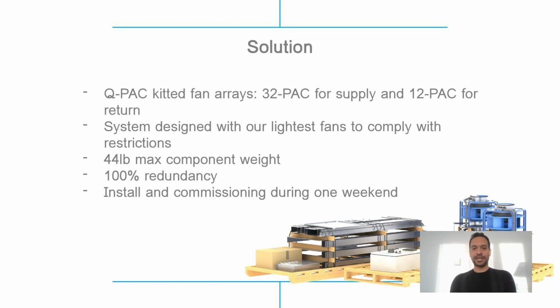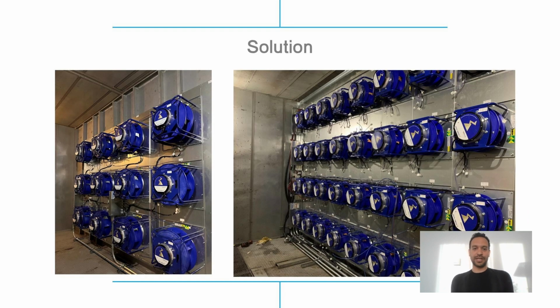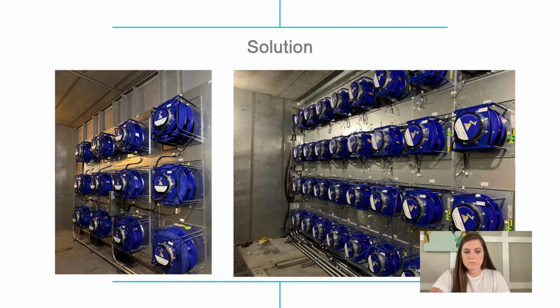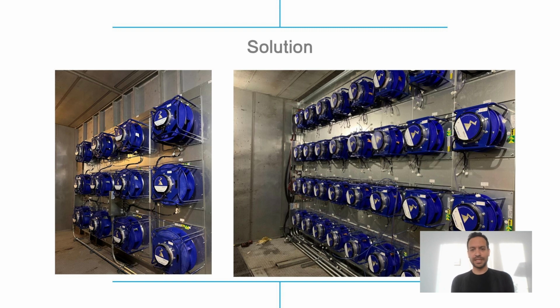And the install and commissioning happened during 1 weekend. So everything was up and running after that 1 weekend that everything was installed. A couple of pictures on the left, that is the return fan, the 12 return fans. And on the right, as you see, it's a portion of the supply fan array. You can notice the wiring isn't done, so it's mid install. So the fans are on the wall, and they're just going to do the wiring between the fans and the quick connect boxes that are on the left.